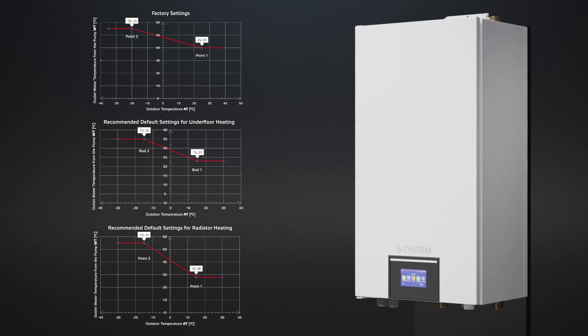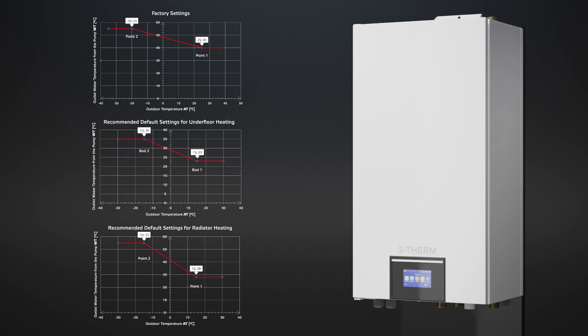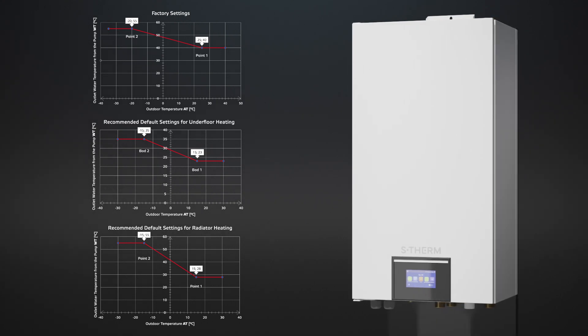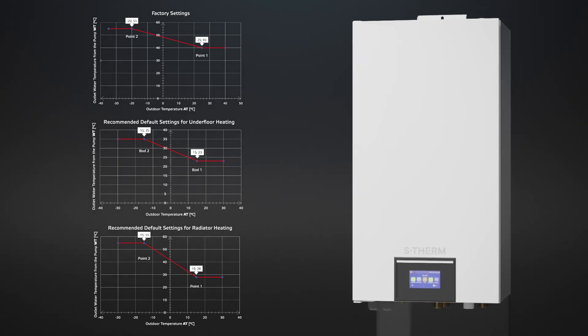Record the heating water temperature, the temperature in the building, and the outdoor temperature. Then set the curve based on these notes. Here you can see the possible default setting.